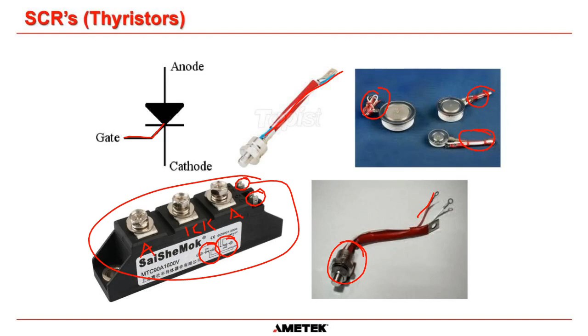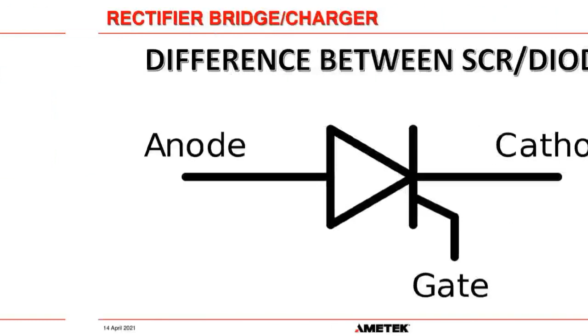And once again, this bottom module here, this is becoming more and more common. There's the gate cathode terminals here. And you can see on the side of the SCR package, it tells you there's two SCRs in here, and I can tell straight away, this is the anode, this is the cathode for both of the SCRs, and there's the anode. And once again, here's a stud-mounted one. They're very, very similar to diodes, except they've got a gate lead.